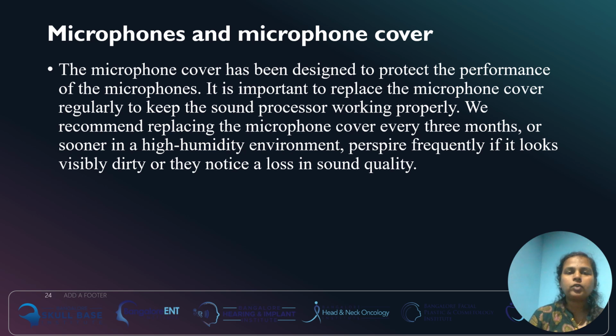The microphone cover has been designed to protect the performance of the microphones. It is important to replace the microphone cover regularly to keep the sound processor working properly. Replacing the microphone cover every 3 months is recommended, or sooner in a high humid environment, if the user perspires frequently, if it looks visibly dirty, or if they notice a loss in sound quality.